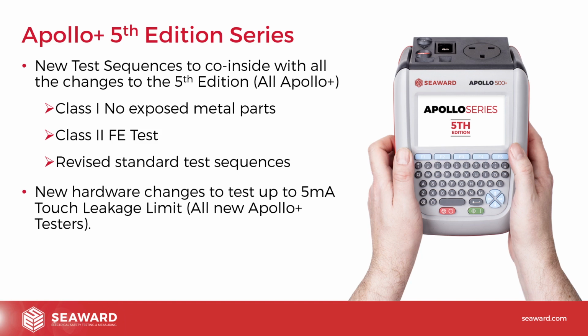So what happens when you put the new firmware on? Well, when you put the new firmware onto existing Apollos, it will just extend the measurement range, but only to 3.5 milliamps for touch current. For protective earth current, protective conductor current, it will actually measure up to 5 milliamps. The circuitry would allow for that. So with the firmware change, you'll be able to do the full 5 milliamp tests for protective conductor current. So that'd be the sort of test you'd normally do on Class 1 equipment. But it's the touch current that actually needs extending.